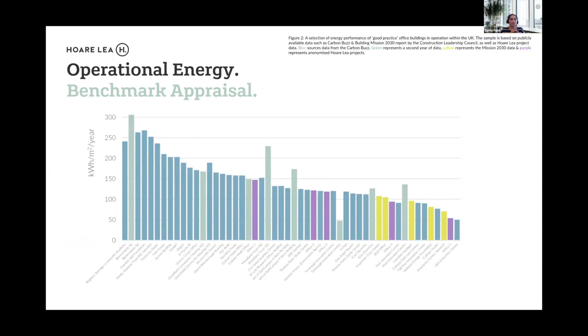But as I said before, it's about understanding how the buildings are performing. We're now more and more focused on understanding how the building is performing. So we go back and review the results of the controls, the energy monitoring system, and the end users as well to make sure that the building is performing the way they want it to. So if some people are saying that it's always cold in the office, we investigate, we find out why it is always cold. Do we need to change the set point? Make sure that the heating comes on earlier rather than later. So instead of starting at say 7 o'clock in the morning, we start at 6, and then instead of finishing at 5 o'clock in the evening, we stop at say 4 or 3:30, because that will help us use the energy more efficiently.